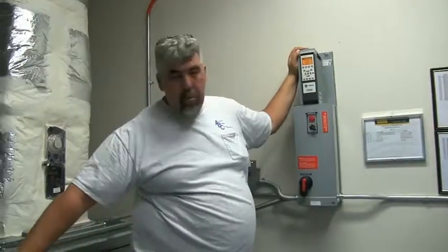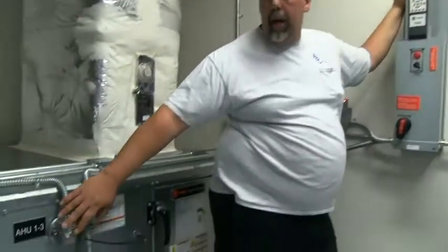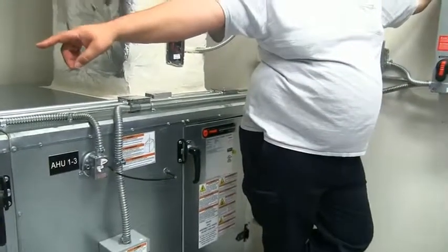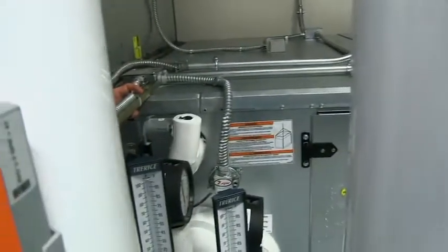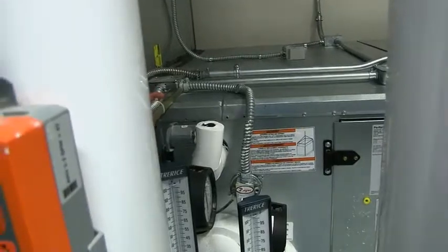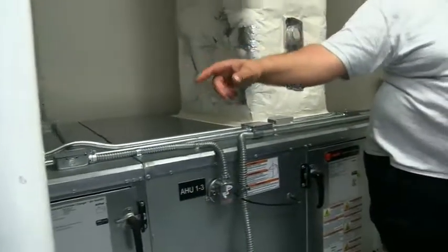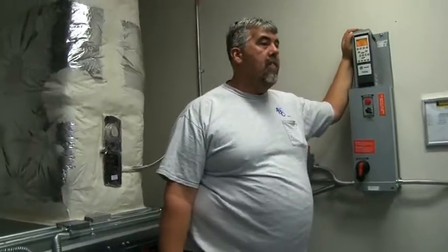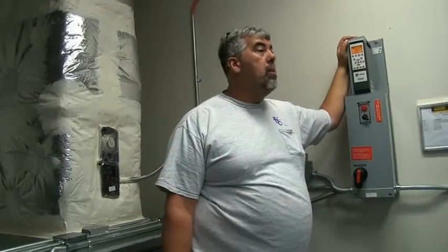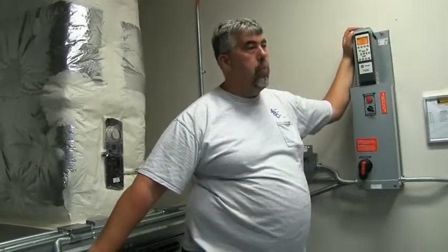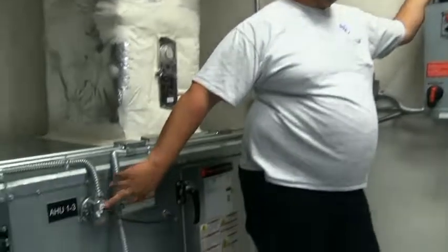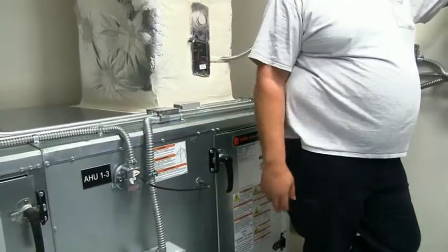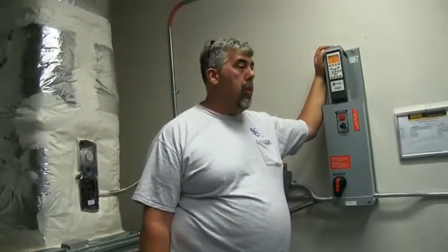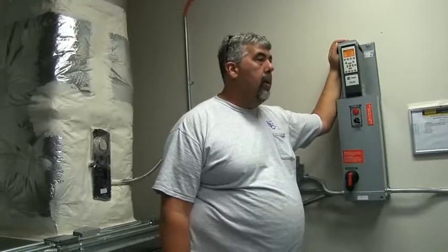Right. Oh, these switches here are your high-low cutouts. If the negative pressure on the filter side of the duct gets too low, it's going to trip the unit. Now this is just like a fire alarm trip. It is a manual reset. These buttons have to be manually pushed. You will have to come here for that. That is also to, if it happens over and over, it will make you want to look into why. You know what I mean?